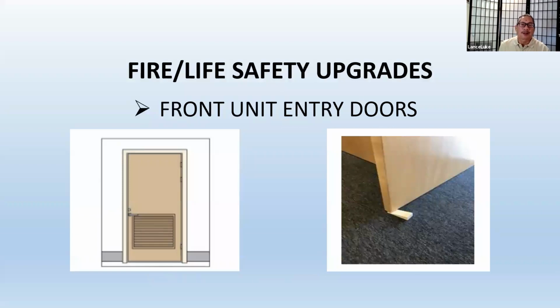Here's something very interesting. Most people do not know that in a condo building or apartment building, your front unit entry door is considered a fire door. And when the door is considered a fire door, it cannot have any louvers in it. It has to be solid. So if you look at the image on the left, that's a front unit entry door to a condo, and there are louvers. Why are there louvers? Well, for ventilation. But guess what? That's not allowed by code. You cannot have any louvers.